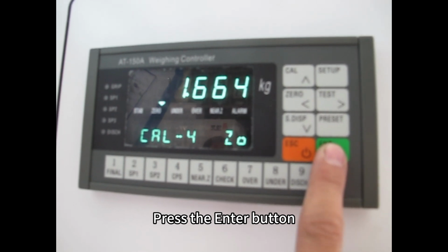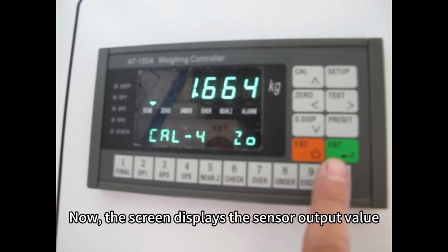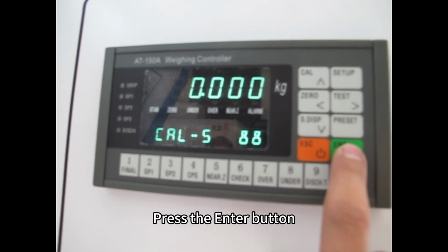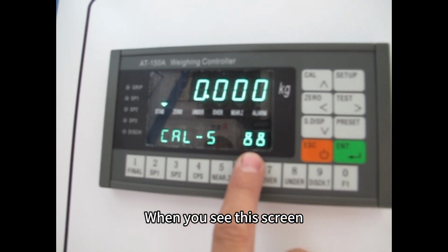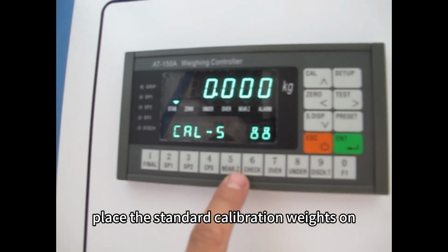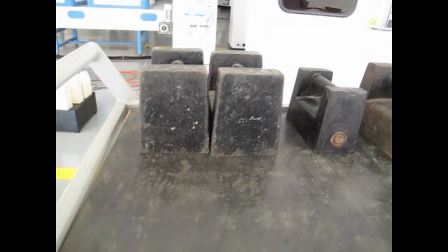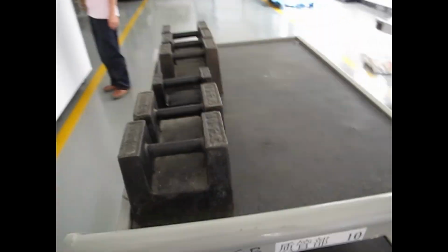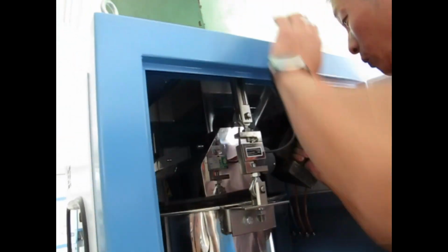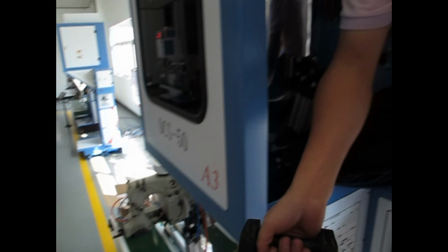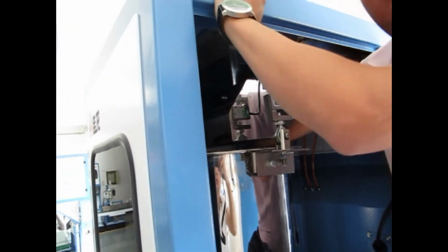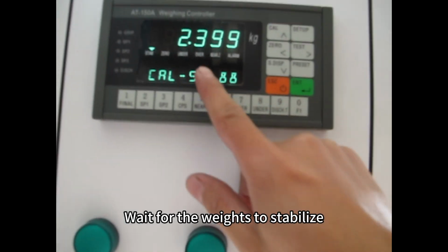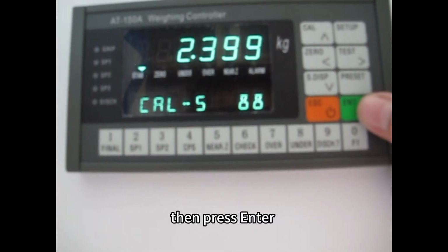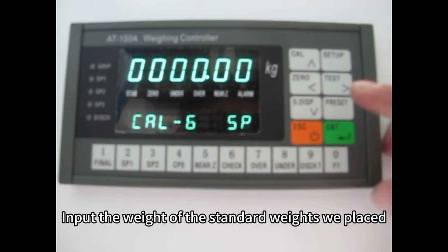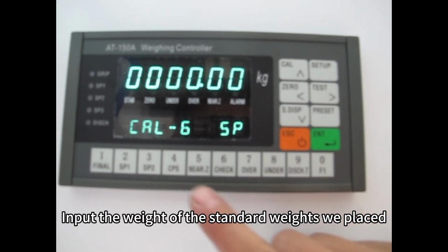Press the Enter button. Now, the screen displays the sensor output value. Press the Enter button. When you see this screen, place the standard calibration weights on. Waiting for the weights to stabilize. Then press Enter. Input the weight of the standard weights we placed.